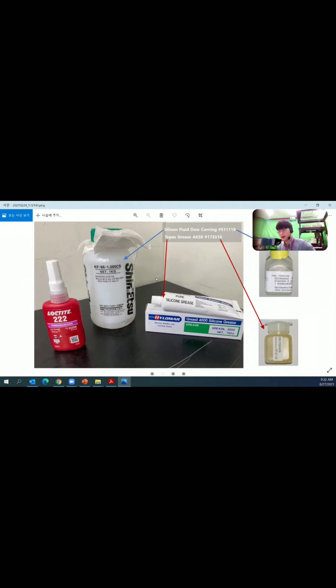To maintain the machine, we have to use two kinds of material. First one is silicone oil, and the other one is grease. On the right side, this is the Hamilton official product. Upper one is oil, the lower one is grease. But actually, I use products I got from the local market. The left one, Loctite, is used when we install the new stop disc to the pipette head.